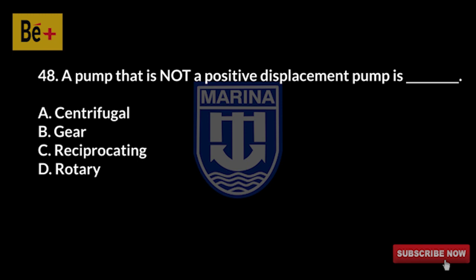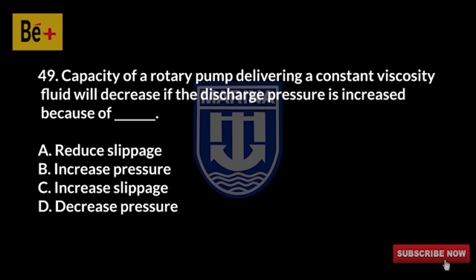A pump that is not a positive displacement pump is: A) centrifugal, B) gear, C) reciprocating, D) rotary. The answer is A, centrifugal. The capacity of a rotary pump delivering a constant viscosity fluid will decrease if the discharge pressure is increased because of: A) reduced slippage, B) increased pressure, C) increased slippage, D) decreased pressure. The answer is C, increased slippage.